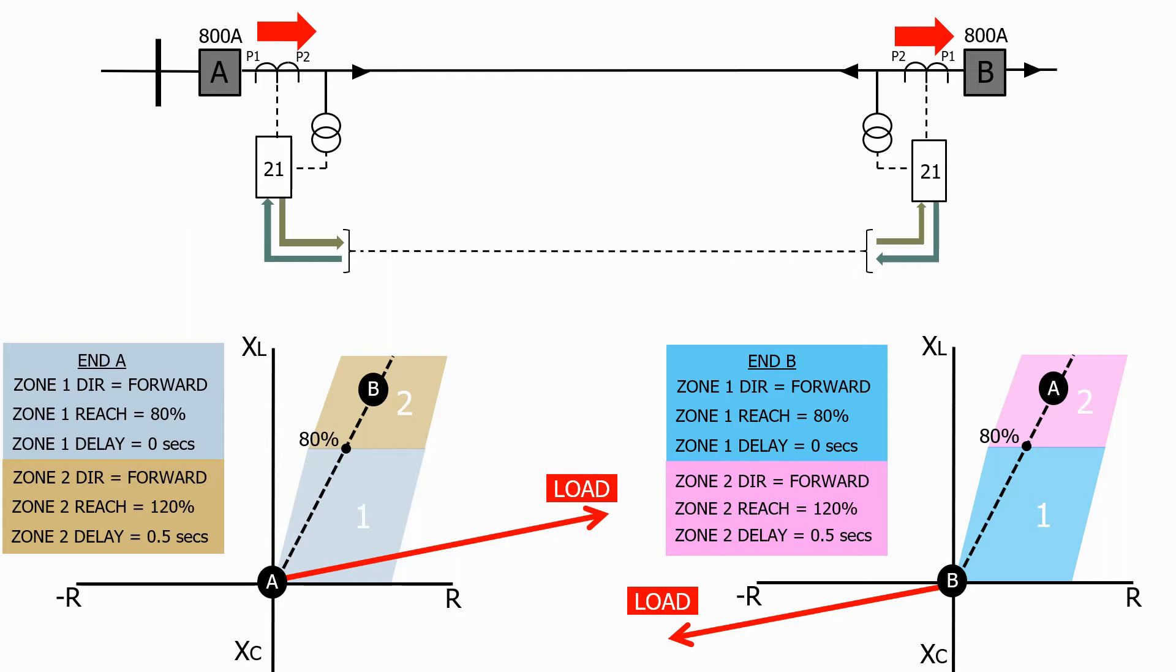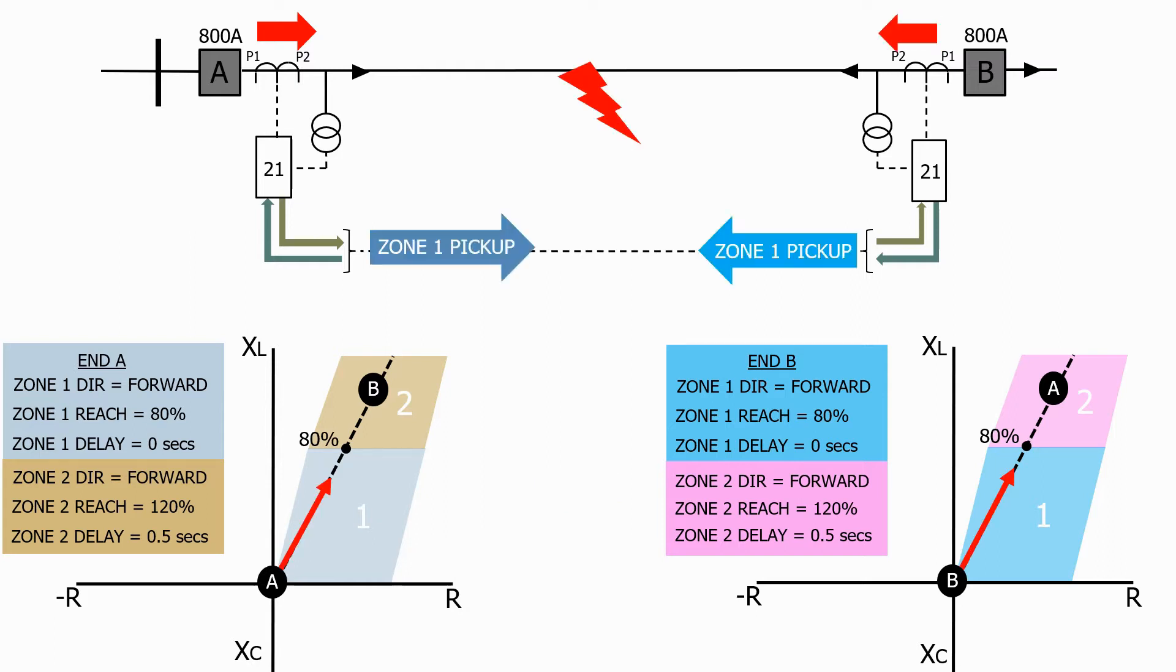Let's now add a fault halfway down the line. Straight away both of the impedance relays will see the fault in zone 1 and send the zone 1 pickup signal down the communication circuit to the relay at the far end.